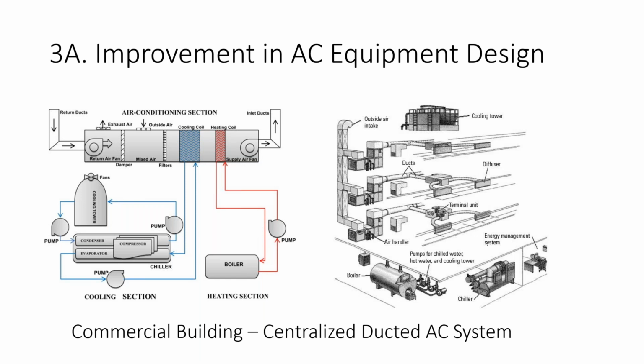Considering the air handling units, we start with the return ducts on the left side, and then the return air fan, and then we have dampers, and outside air, which mixes with the return air. We have cooling coils, heating coils, and then a supply fan. The cooling coils get their chilled water from a chiller, which in this case is an evaporative chiller. It uses a cooling tower, and it uses a refrigerant as the medium to cool the water. It has two heat exchangers, a condenser and an evaporator, to make our water chilled, which we will eventually use to make our space cool.